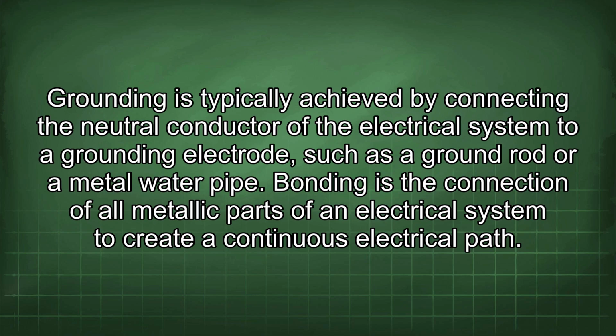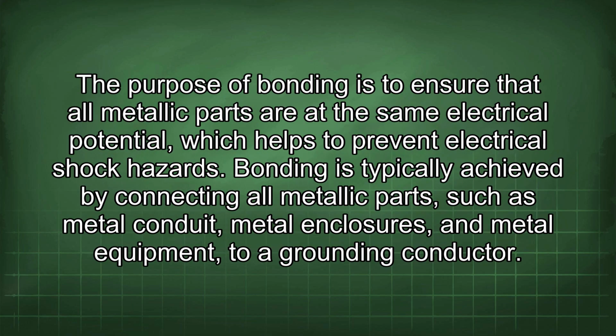Bonding is the connection of all metallic parts of an electrical system to create a continuous electrical path. The purpose of bonding is to ensure that all metallic parts are at the same electrical potential, which helps to prevent electrical shock hazards. Bonding is typically achieved by connecting all metallic parts, such as metal conduit, metal enclosures, and metal equipment, to a grounding conductor.